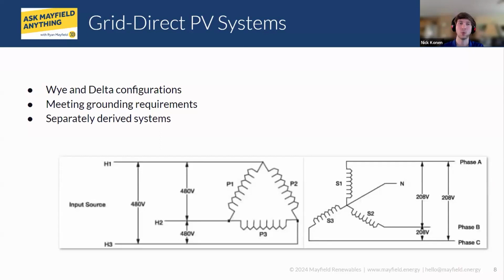We certainly can do YY, if you have a utility that really wants to see Ys on both. That definitely is a possibility though. We do see sometimes that can cause some issues though with the neutral on the utility side there. If it is bonded as well, it often can act as a return path for neutral flux. So sometimes that has caused some heating problems in the neutral as well. So functionally, we prefer to go with the delta there on the grid side.